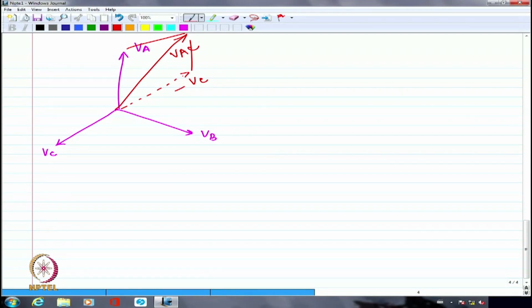So we have essentially a 30 degree phase shift between phase voltages and line voltages. But what I am actually applying is a line voltage. We generally bring only 3 terminals out of a transformer, whether it's star connected or delta connected, it hardly matters - most of the time only 3 terminals come out. These 3 terminals connect to the 3 terminals coming out of your 3-phase power supply.